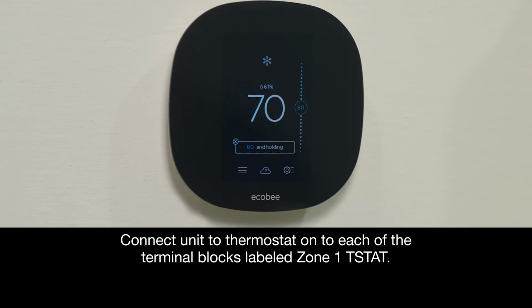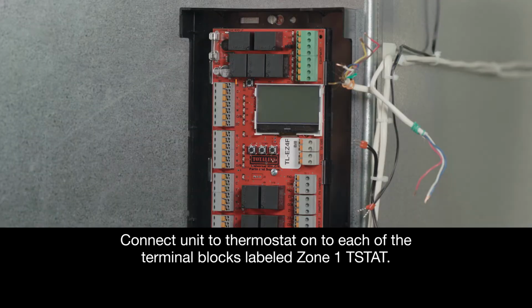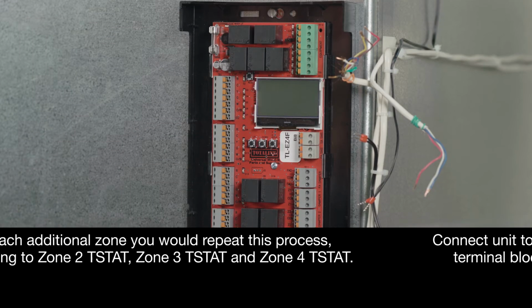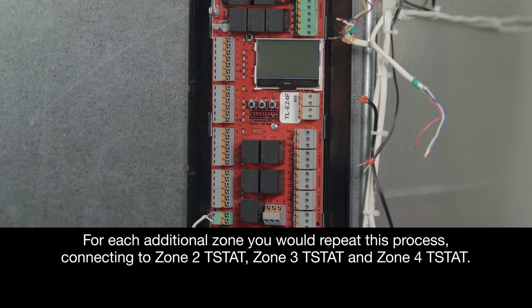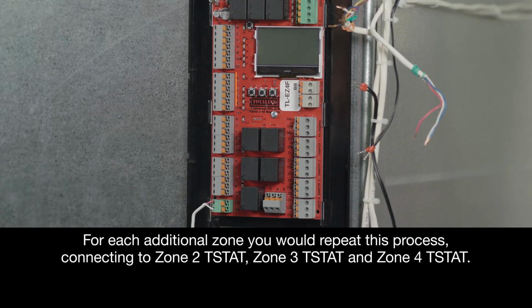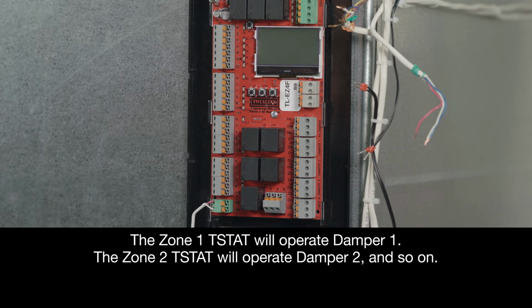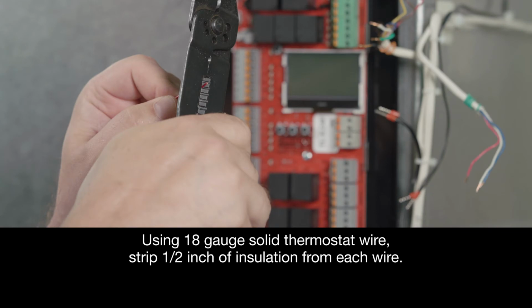Today, we're connecting this unit to an Ecobee 3 lite thermostat onto each of the terminal blocks labeled Zone 1 T-stat. For each additional zone, you would repeat this process, connecting to Zone 2 T-stat, Zone 3 T-stat, and Zone 4 T-stat. The Zone 1 T-stat will operate damper 1. The Zone 2 T-stat will operate damper 2, and so on.